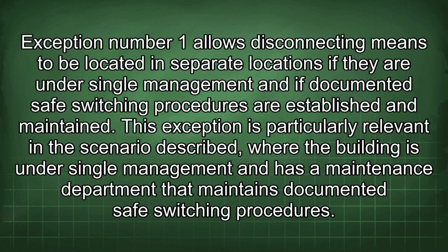Exception number 1 allows disconnecting means to be located in separate locations if they are under single management and if documented safe switching procedures are established and maintained. This exception is particularly relevant in the scenario described where the building is under single management and has a maintenance department that maintains documented safe switching procedures.